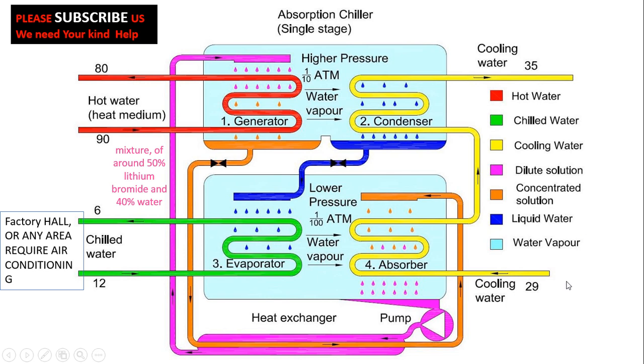In an absorption chiller, vapors are generated and absorbed due to pressure differences — that is why it is called an absorption chiller. The refrigerant used is a lithium bromide and water solution, typically in a 50/50 or 60/40 ratio. Some absorption chillers use ammonia and water, but in this video we are explaining the lithium bromide and water type.